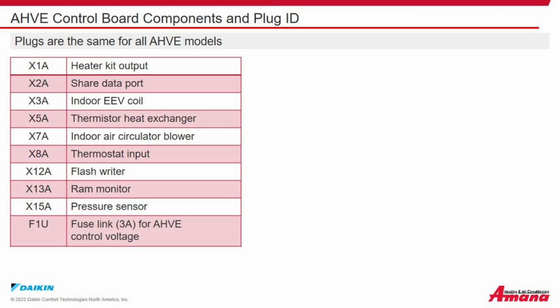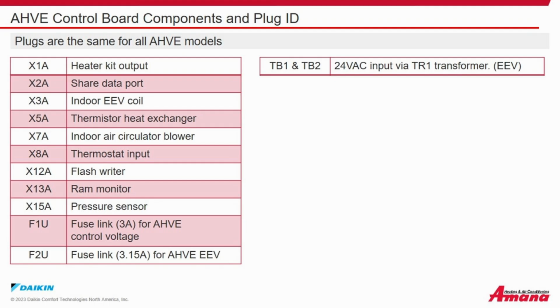F1U is a fusible link, 3 amp, for the control voltage for the AHVE. F2U, fusible link, 3.15 amp, for the electronic expansion valve in the AHVE. TB1 and TB2, 24 volt AC input via the TR1 transformer for the electronic expansion valve. TB3 and TB10, 24 volt input from the TR2 transformer in the AHVE.